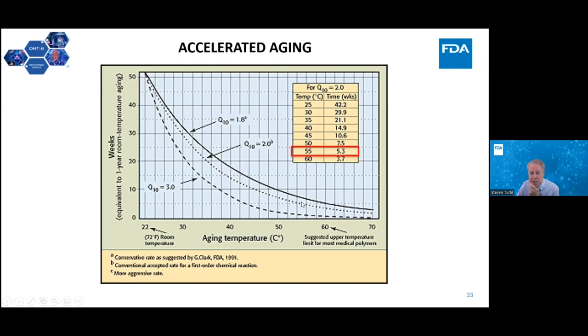Accelerated aging time. This is basically the equation that you can find in college physics books. For 365 days of Q10 of 2, if you take this number here, which is the accelerated aging temperature, if you're going to accelerate it at 55 degrees, but your standard room temperature storage temperature is 23 degrees. Subtract, and divide by 10. When you subtract this from this, divide it by 10, you get a 3.2. You take that Q10 factor to the power of 3.2 and you get 9.19. Divide 365 days by 9.19 and you've got 39.72 days. Accelerated aging equals 1 year of real-time aging.